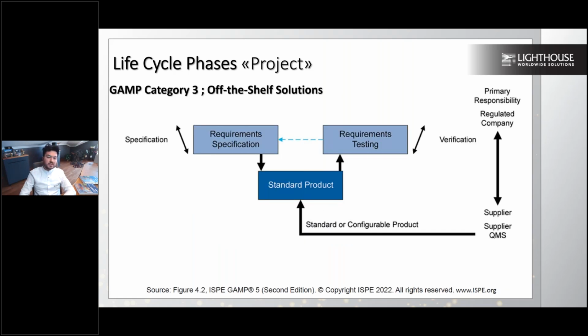Looking at this V scheme, if this is GAMP category 3, which is off-the-shelf solutions, we have a simple requirement as a specification and simple verification steps. For example, you have a data logger with specific software, not configurable, that you buy from the market. It arrives at your company, then you apply the IQ and OQ protocols to verify your specifications are met by the documentation—this is the off-the-shelf solution.